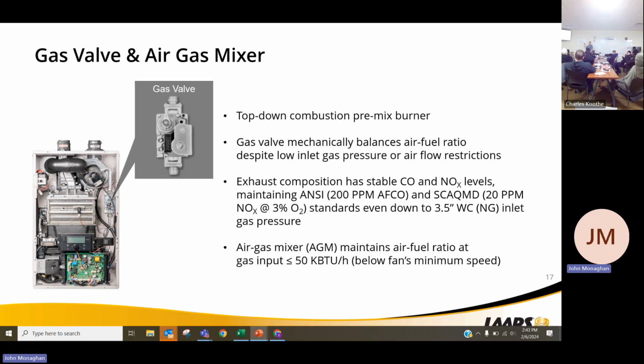Gas valve. It's going to look very similar to the ones on our heat only products. Same thing. We're only going to be adjusting it in low fire. You're going to need your T40. Do we still have the screwdrivers for them? The little gas valve screwdrivers? We have a little screwdriver that works wonderful for actually working on them. And I use the pen clip on it as a dial, so I know how far I am adjusting it.